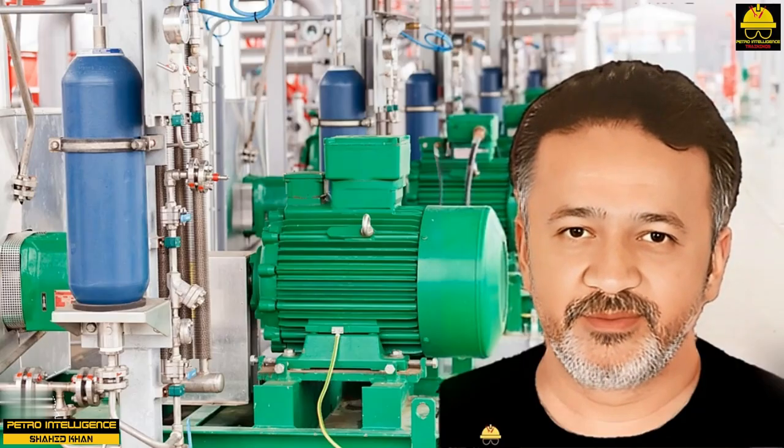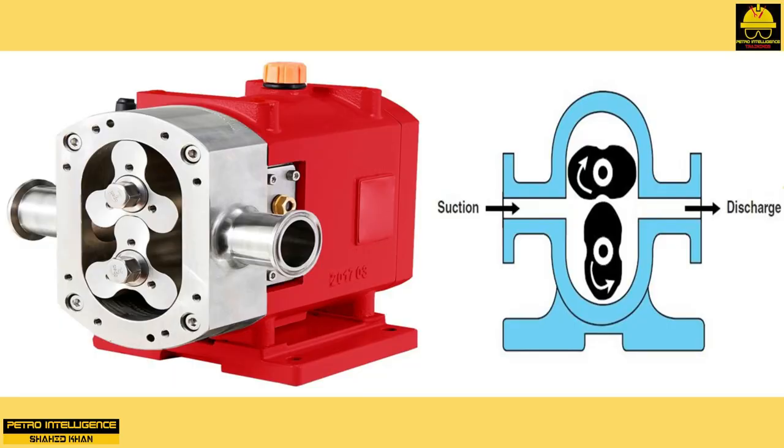Lobe pumps. Lobe pumps, as shown in picture, have two rotating lobe-shaped screws that mesh during operation. As the lobes turn, voids are created that carry liquids around the outside of the pumping chamber. In a lobe pump, a set of external timing gears and bearings allows the lobes to turn in unison without making contact with each other. This feature allows the pump to transfer a wide variety of fluids. Because the lobes do not touch, the pump can run empty without damaging the system.